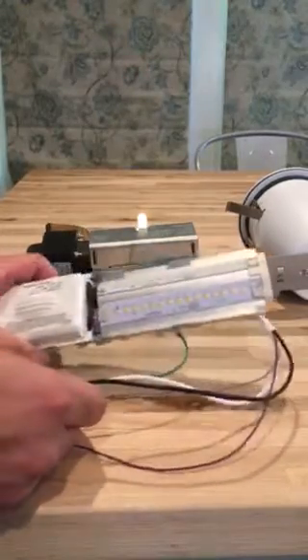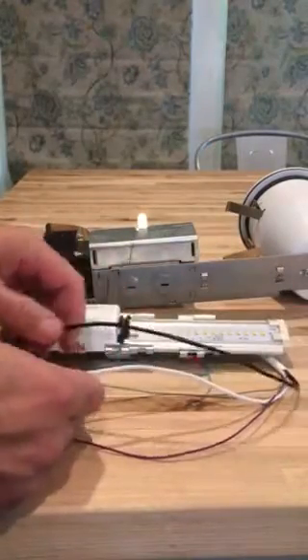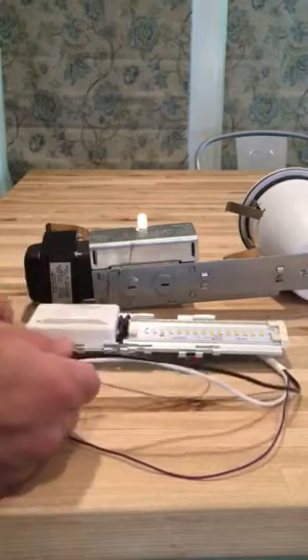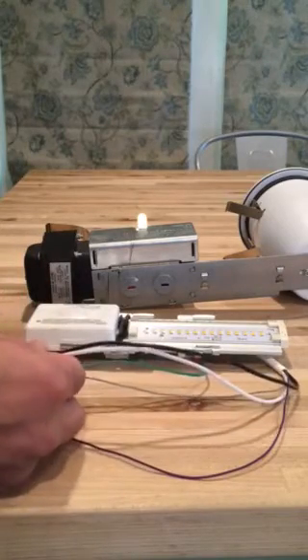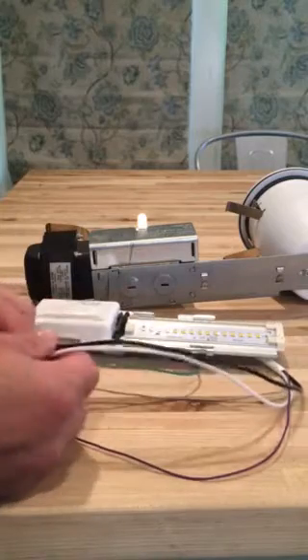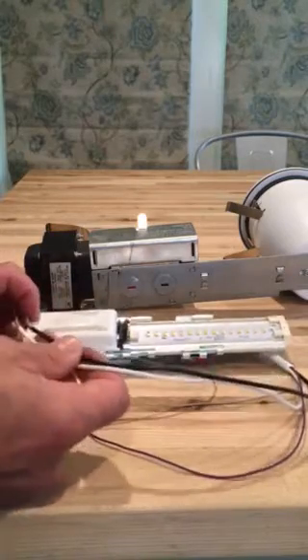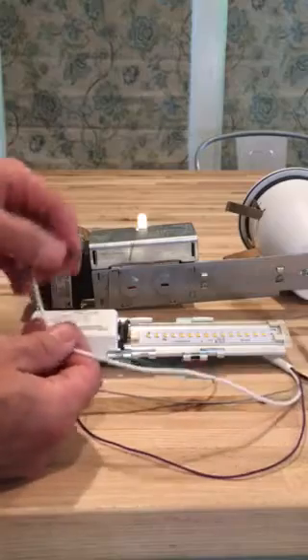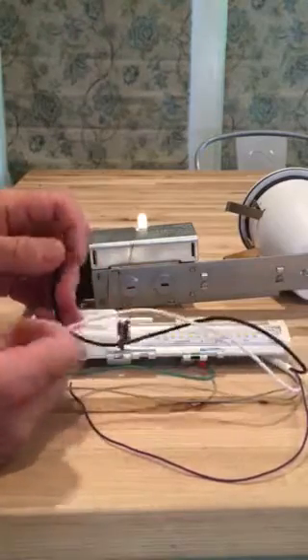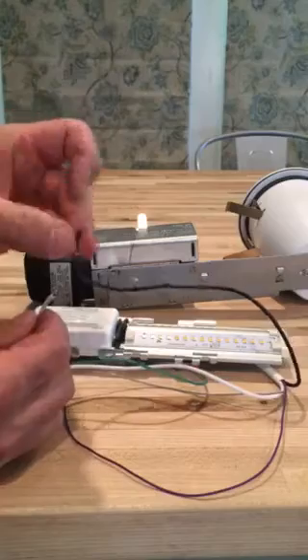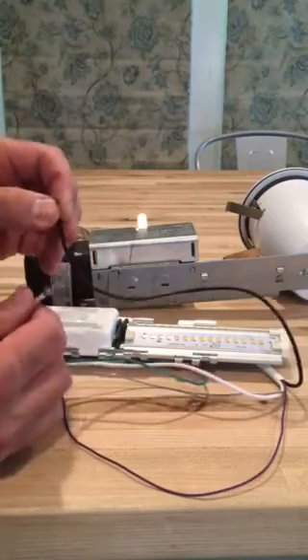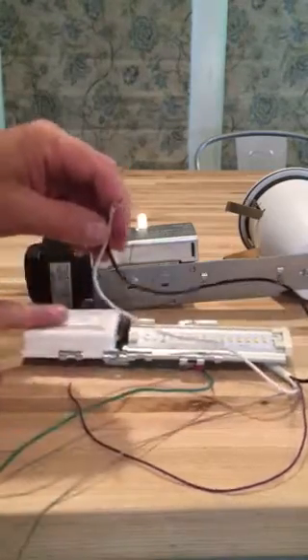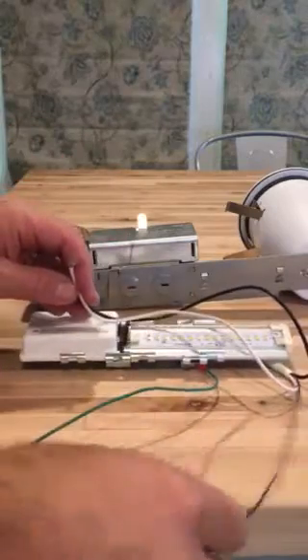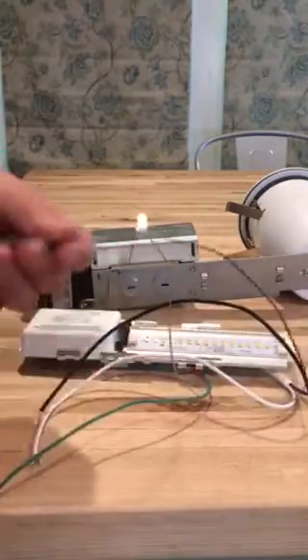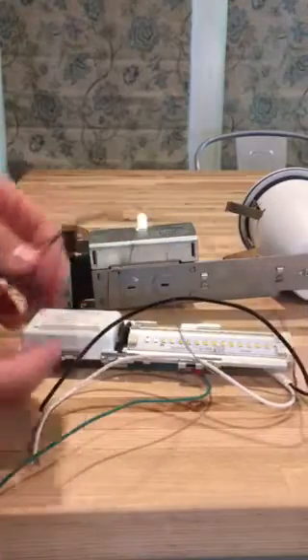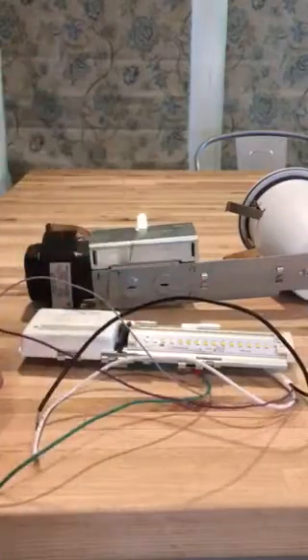This is a replacement module for an LED fixture, but I want to go over this so you can understand a different nomenclature for low voltage dimming. I have another video on 0 to 10 volt basics and I'll cover this more in depth, but for 0 to 10 volt, sometimes called low voltage dimming, we have line voltage, 120 or 277, that gets switched on to this. This is our LED driver, and we get 0 to 10 volt. This is the low voltage portion, which goes back to a dimmer and adjusts the total output of this fixture.